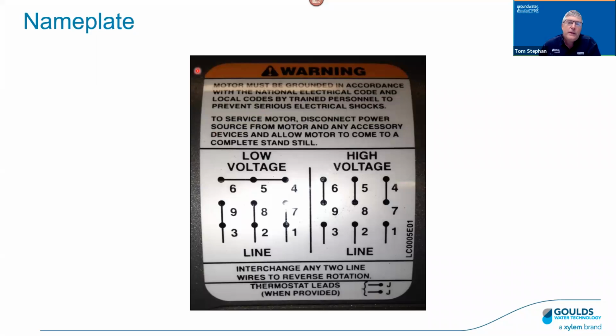Okay, the other thing that you will see on a motor like this is the wiring diagram. We can see here we've got low voltage and we've got high voltage. With this type of motor, you're going to open up the conduit box and there are going to be 9 wires sticking out. They are going to be numbered, but the installer has to wire that up based on whether they want low voltage or high voltage. If you remember our scenario from the nameplate, low is 208 or 230 and high was 460. Everything to the left of the slash is low and to the right of the slash is high.